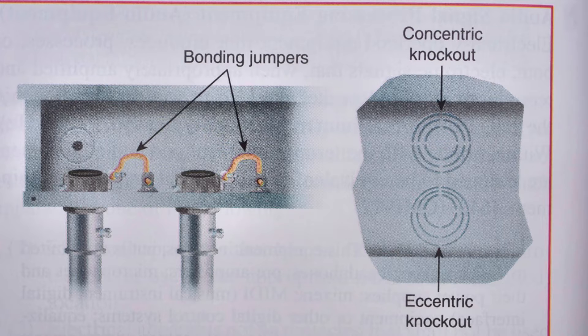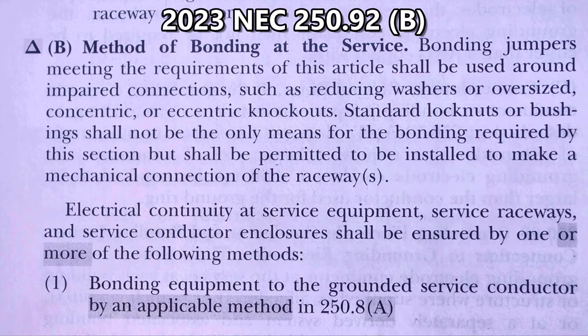These concentric and eccentric knockouts can be found in panels and electrical boxes of all sorts. This is NEC 250.92(b) — method of bonding at the service.